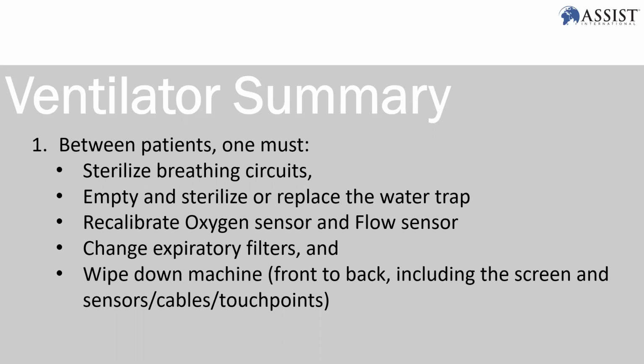So when you talk about ventilators, the summary between patients: one must use a sterilized breathing circuit. When you change patient, you need a new or newly sterilized circuit. Empty and sterilize, or replace, the water trap, all that. Recalibrate the oxygen sensor and flow sensor. Change the expiratory filter and wipe down the machine front to back, including the screen, sensors, cables, and touch points. This is very important when you look into the ventilator device.